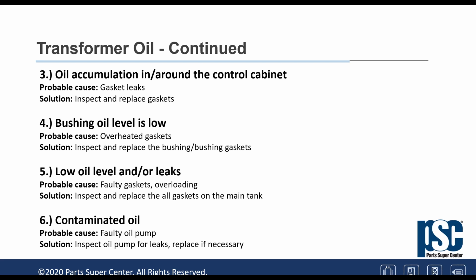The first thing I would look at would be the pressure in the tank. Those transformers, especially the ones with a nitrogen blanket or the ones with no atmosphere system, are designed to work at about 5 to 6 psi, which is normally what happens in summertime. But gasket leaks are usually the source of this oil on the ground or around the control cabinet or wherever. The beauty about oil is that it doesn't go away by itself. So if there is a leak, it stays there even after a couple of months. A visual inspection tells us what's happening to the unit.